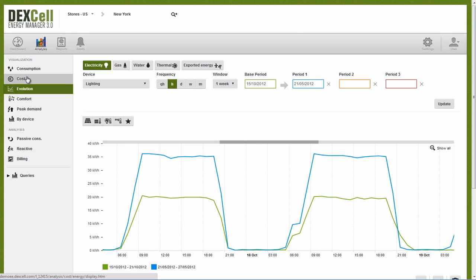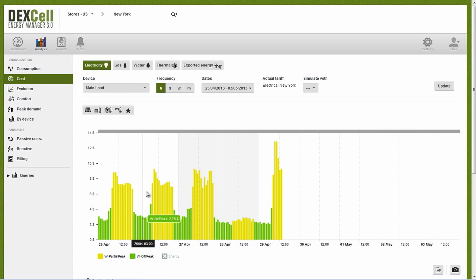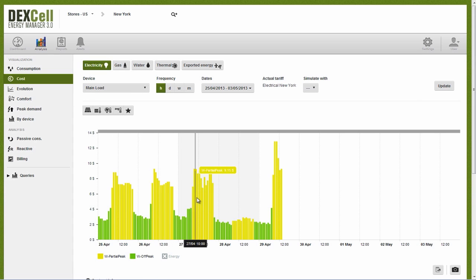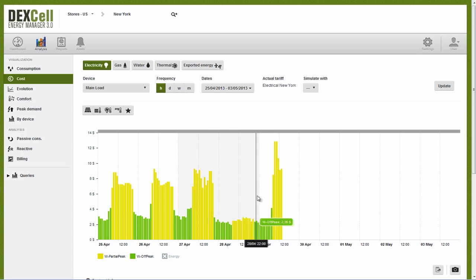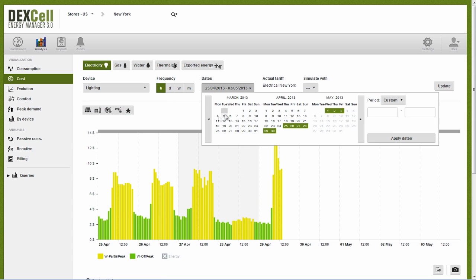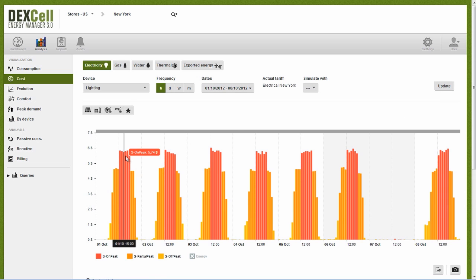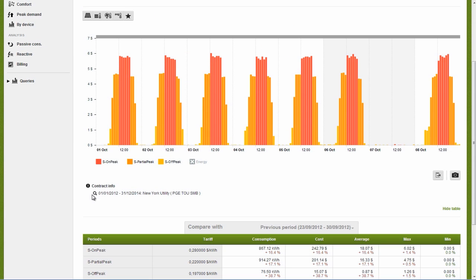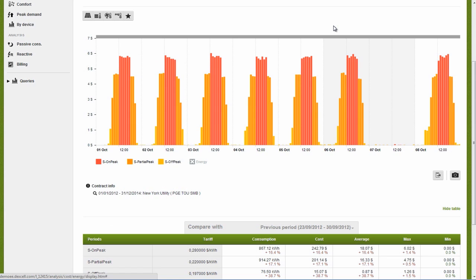For this, we simply go to the cost screen where we can see in real time exactly how much money we are spending according to the particular tariff. If we look at the cost of lighting at the New York location, we see a cost of over $3,000 a month. The graphic shows us that most of the consumption comes from the peak level, which corresponds to the contracted tariff 3.0a.